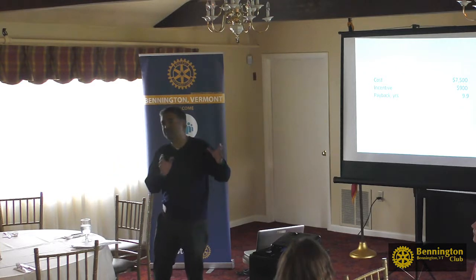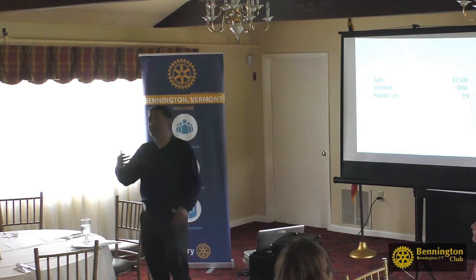The biggest thing is, if you're building a new home, that's the time to look at ground source. If you're building new, the incremental cost of installing propane or oil-fired furnaces and all the ductwork versus doing a ground source heat pump — that delta is much narrower, so people can easily justify the added cost.